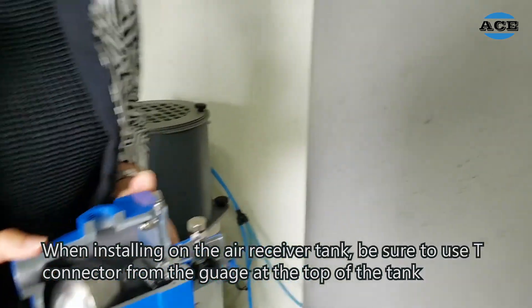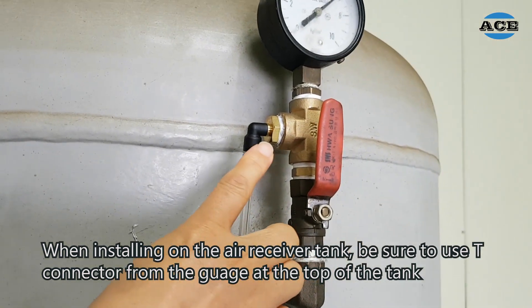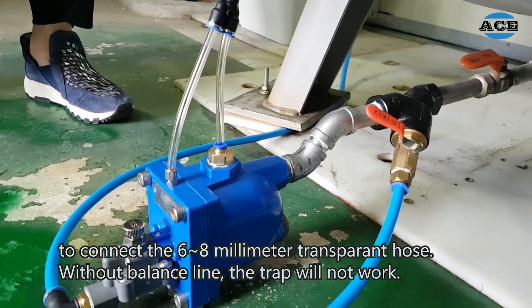When installing the air receiver tank, be sure to use the T-connect from the gauge at the top of the tank to connect the 6 to 8 mm transparent hose. Without the balance line, the trap will not work.